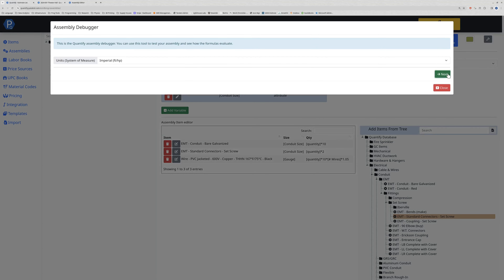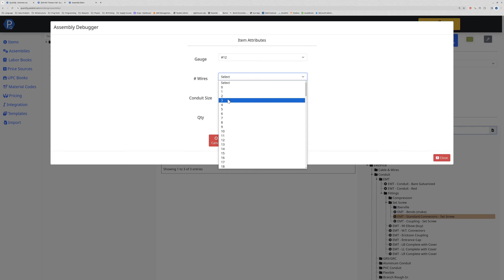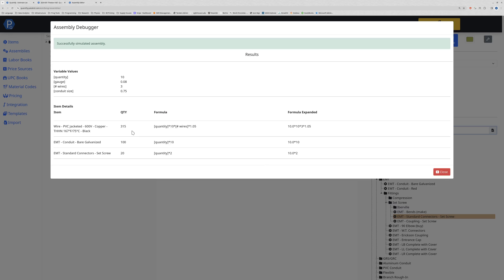To test it out, I can either use a test estimate or come in here and select the assembly debugger and fill in the same information. Selecting number 12 with three wires in a three-quarter inch conduit with 10 of these, clicking commit shows me I'm going to get 315 feet of wire, 100 feet of conduit, and 20 connectors - that is what would be evaluated in my estimate.